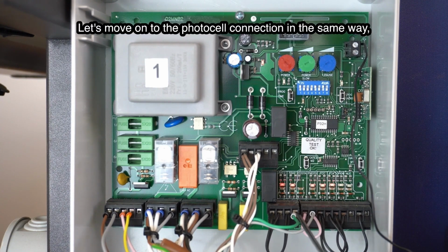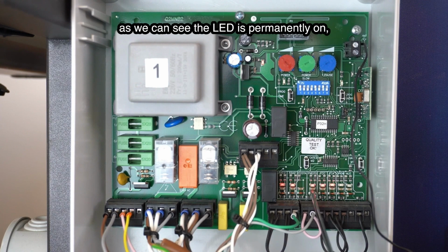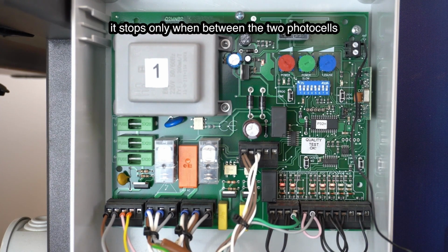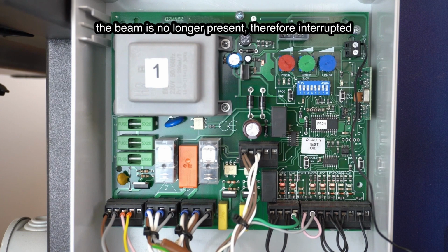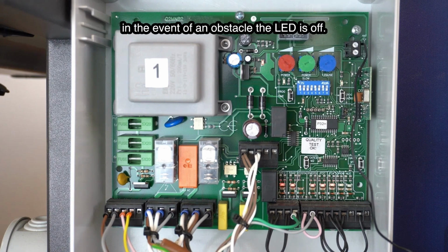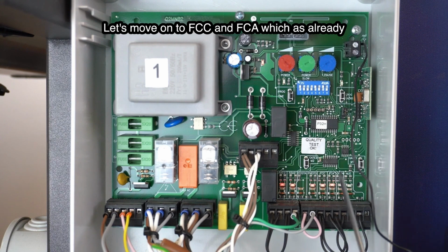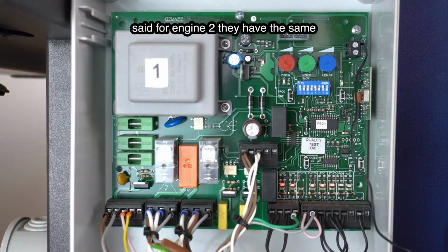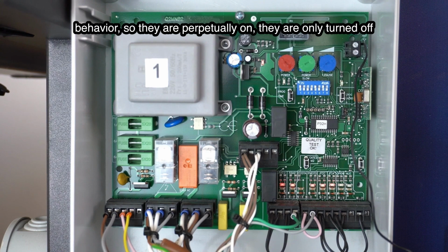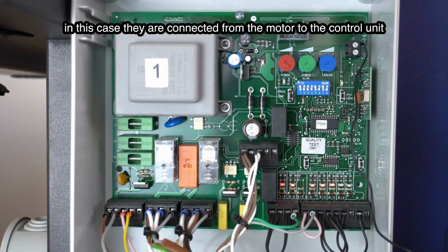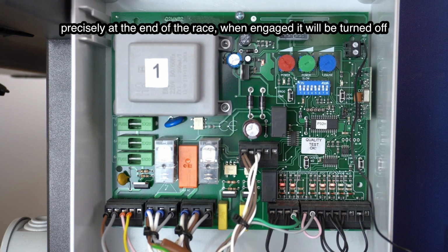Let's proceed the same way to connect the photocell. The LED is permanently on. If something interrupts between the 2 photocells, the beam is no longer present, cut by an obstacle, and the LED goes off. Let's move on to FCC and FCA of motor 1, which have the same behavior: they are permanently on and only turn off when the limit switch is engaged.